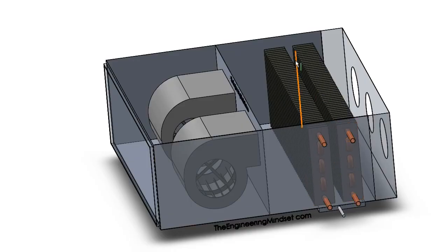Now the cooling coils, or the heating and cooling coils, do not necessarily have to be on this side of the fan. It kind of varies by manufacturer. So these coils could also be before the fans, so that the air is coming in, passing through the filter, passes over the coils first, and then is sucked by the fans and pushed out. But this is a very common example. Now I've put in this model that there are the coils and that there's water passing through these to give up the temperature as required.